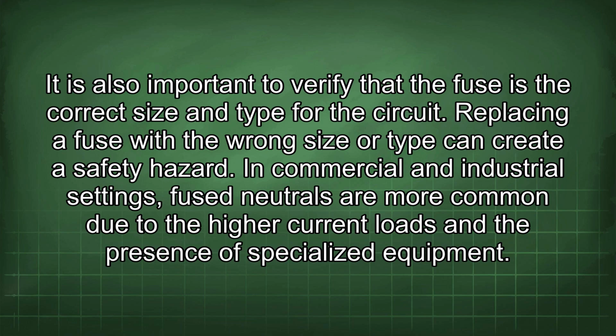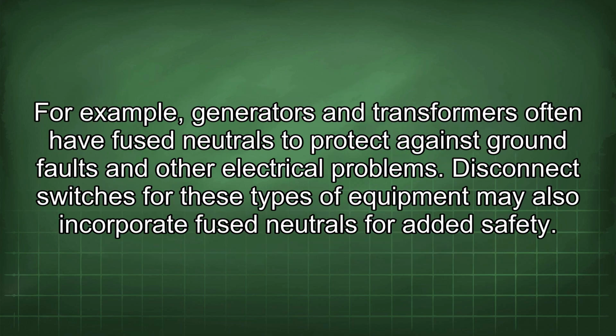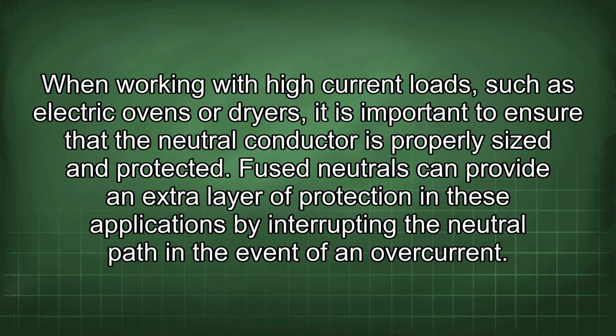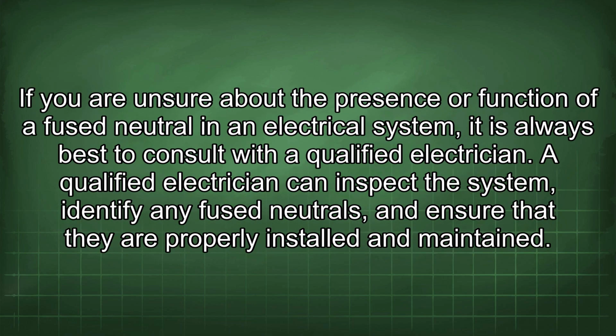In commercial and industrial settings, fused neutrals are more common due to the higher current loads and the presence of specialized equipment. For example, generators and transformers often have fused neutrals to protect against ground faults and other electrical problems. Disconnect switches for these types of equipment may also incorporate fused neutrals for added safety. When working with high current loads, such as electric ovens or dryers, it is important to ensure that the neutral conductor is properly sized and protected. Fuse neutrals can provide an extra layer of protection in these applications by interrupting the neutral path in the event of an overcurrent. If you are unsure about the presence or function of a fused neutral in an electrical system, it is always best to consult with a qualified electrician.